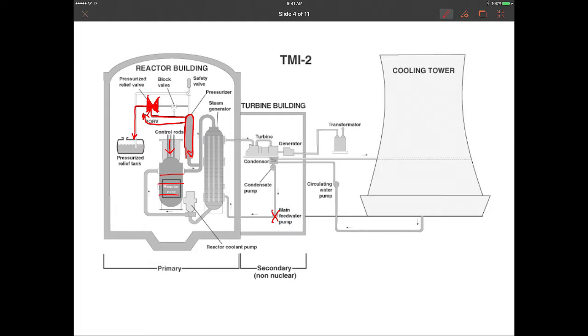The primary side pressure dropped so much that the reactor coolant pumps eventually had to be shut off to reduce cavitation. This is the reactor coolant pump here. When the water began to drop and there's no water in the coolant pump, then it begins to cavitate. And if it cavitates and vibrates too much, you can experience a breakage in the pipe known as a large break LOCA, loss of coolant accident.